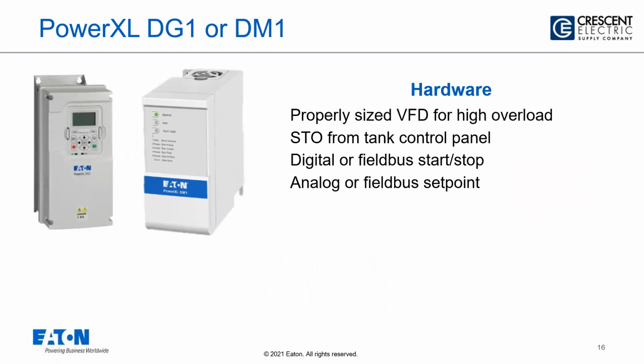Obviously, you select a properly rated DG1 or DM1 drive, and these drives have safe torque off. From the tank control panel, you can enable or disable the safe torque off and use that for protection. The start and stop can be either through digital inputs or by field bus, and the analog feedback or the set points can be given by both analog or field bus.